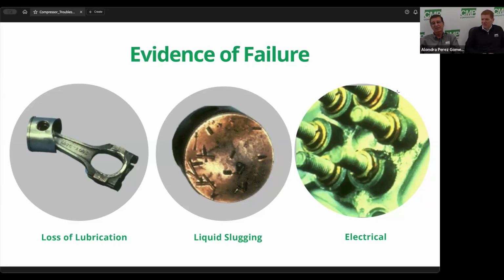And so they're just not designed to run 410A. So that's one of my sticking points that I always try to put in there. Other than that, like I said earlier, find out what causes the compressor to fail, or you're just wasting your time there. Oh, for sure.